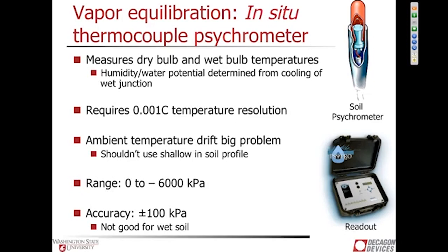So you need to be able to resolve temperature differences of about 1,000th of a degree C. And that may sound pretty simple, but it is not simple at all. And there are only a few measurement devices that are able to make that type of measurement. That's a nanovolt level signal, and it's really difficult to make those measurements. So one of the big drawbacks of the thermocouple psychrometer is that even if the psychrometer is pretty cheap, the readout unit, either from Wescor like you see down here, or if you're using a Campbell Scientific logger, those are pretty expensive and also pretty complex. You have to have some skill to be able to use these.